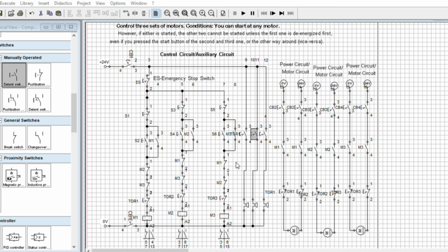TOR2. TOR3. Or OL1, OL2, OL3 in US standard. Okay, that should be directly connected to the lines. Do not connect here, so it will not be controlled by the emergency stop push button. You can have as many as three of this, one here, one here, one here. It depends on your design and where the motors are located in actual.